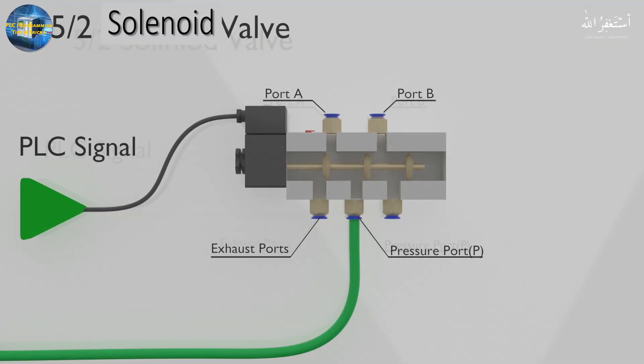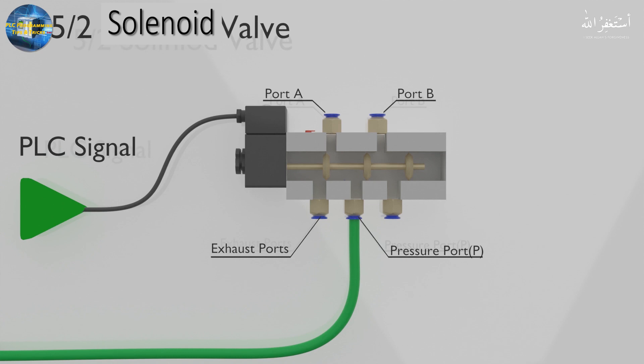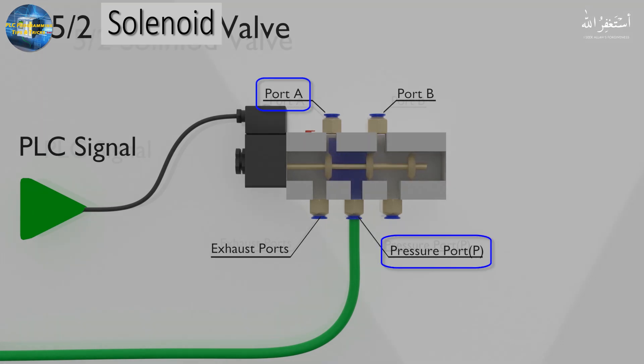The 5/2 way valve has 5 ports for compressed air. One of these ports is the P port — it is the pressure port where compressed air enters the valve. There are two other ports: port A and port B. The pressure port is linked with either port A or port B when the spool inside the valve moves.